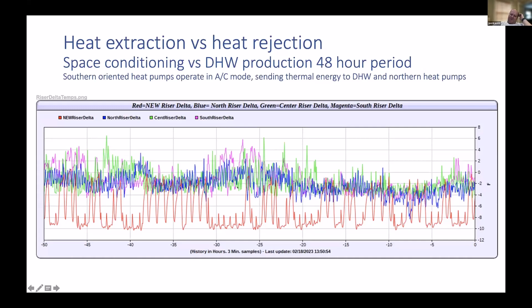And this is again looking back 48 hours or 50 hours here. And the blue line is the amount of heat extracted, the delta T of the loop field, coming from the northern portion of the building. You can see it sometimes dips down to like -8 delta T. So we are actually extracting a huge amount for the northern portion of the building from the loop field. The red line here is the hot water production. When those big heat pumps turn on, and when they both turn on at the same time, we're looking at a -10-degree delta T. So we're pulling out an enormous amount of energy just for hot water production.